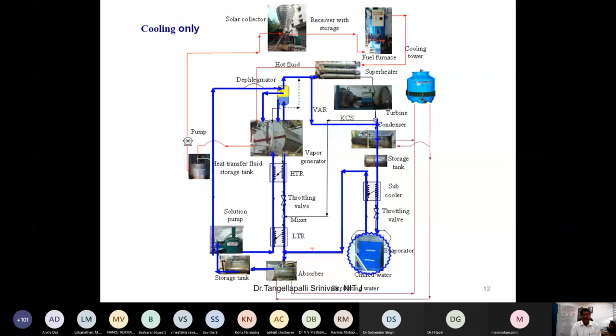Third model, see, this is the third version of this cooling cogeneration cycle. In this third version, it is also called a once-through cycle. Why is it a once-through cycle? The entire working fluid, 100% of the working fluid, is moving through all the components without any separation or bypass. There is no bypass in this cycle. In this cycle, see, the working fluid is entering the superheater, turbine, condenser, throttling, evaporator, and thermal compressor.